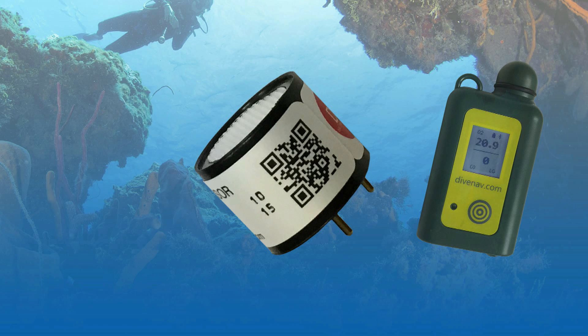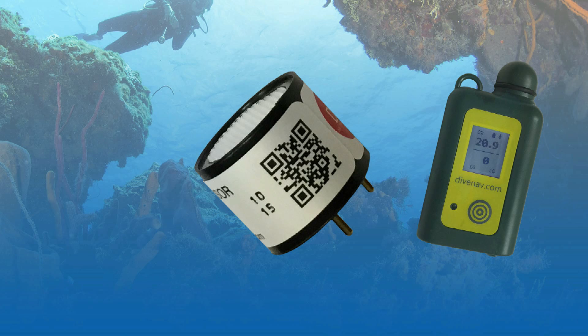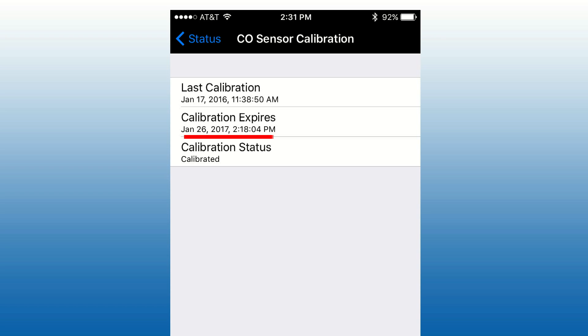Q2 contains a carbon monoxide sensor that should be fully calibrated at least once a year. You can use this smartphone to check when the current carbon monoxide sensor calibration expires.